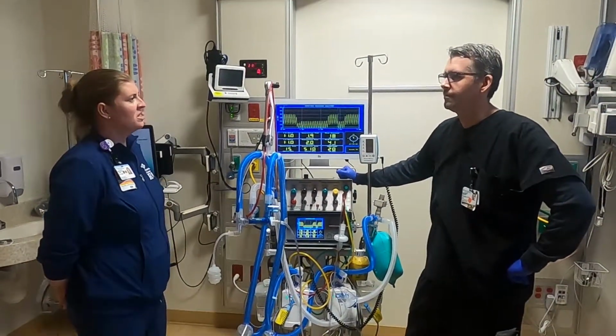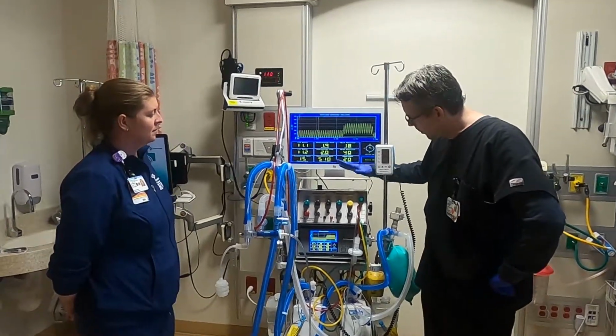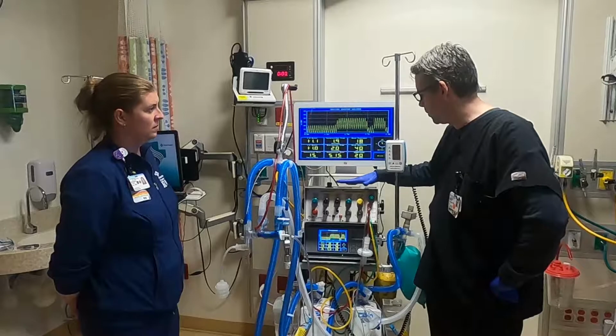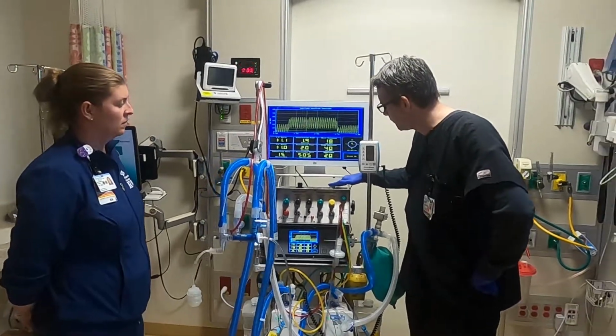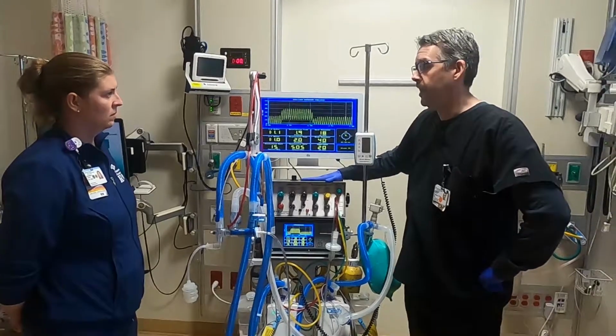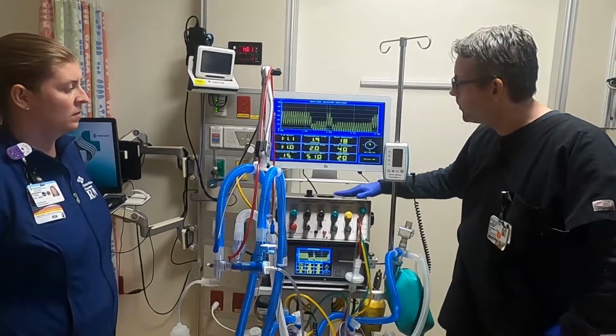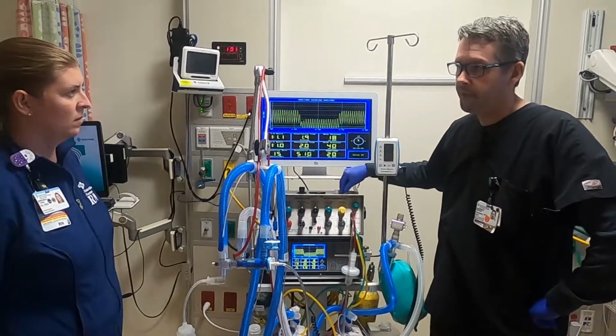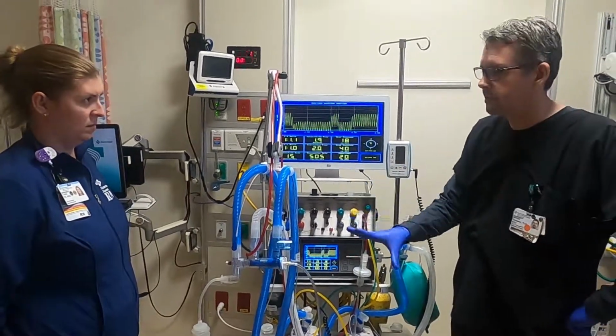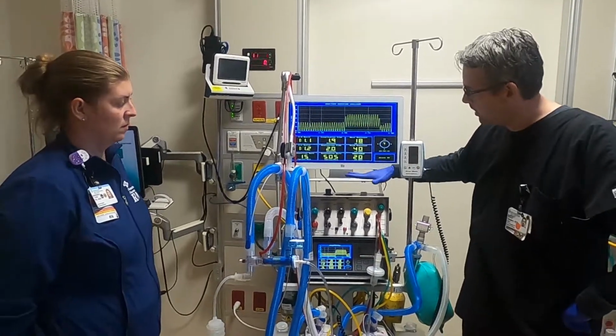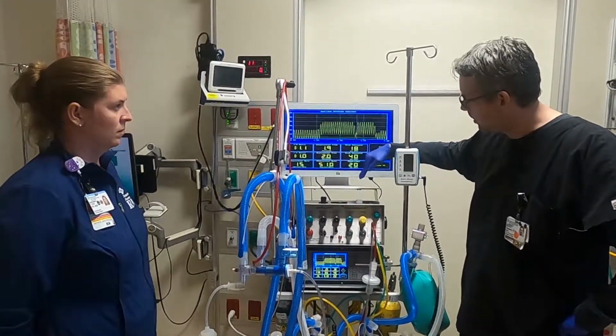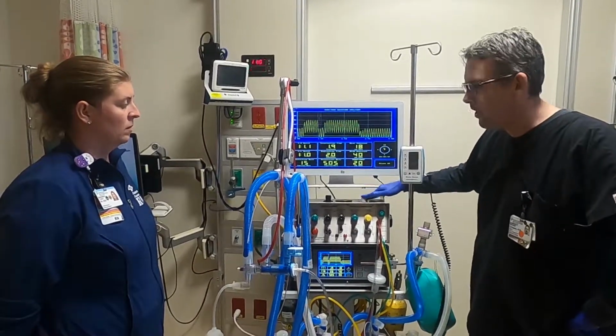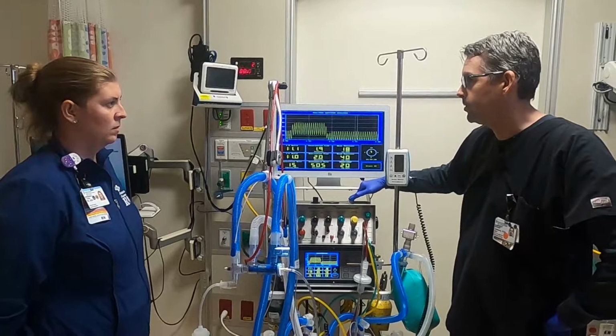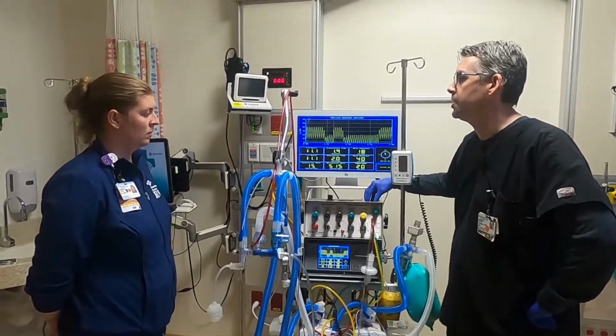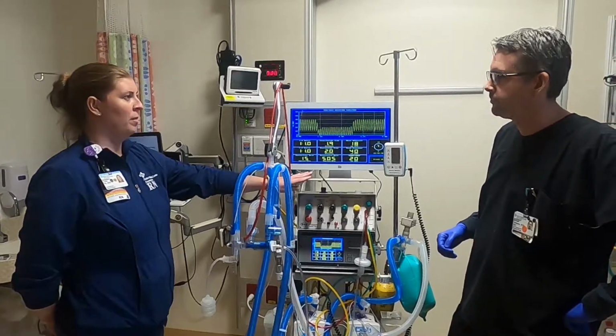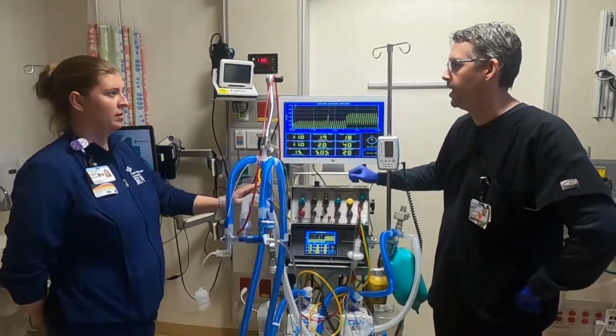So Mike, what do I do if my patient's desatting? If your patient is desatting on this ventilator, the only move you can really make is the FiO2, which is right here. And then call your RT right away. If you have to make a large adjustment in FiO2, it will affect the settings on the ventilator because it's all based on flow and it's all being driven by the pneumatic pressures. So changing the FiO2 by greater than 10% could change the settings on the ventilator itself. Okay. So you're saying I'm only allowed to touch the FiO2 button? That's correct.